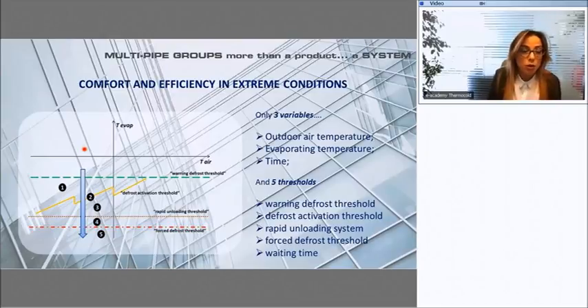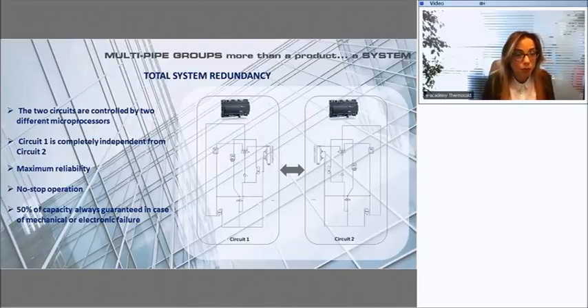At the end, last but not least, we have the digital defrost. As you may know, the digital defrost is a sophisticated algorithm developed by Thermocold. So we are the owner of this technology. And the digital defrost is able to minimize the number of defrost cycles, the time of each defrost cycle, and at the end also the number of unnecessary defrost cycles.